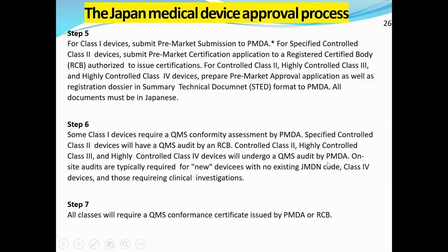So as you go higher and higher, more risk is involved. That is why an audit is required. So Japanese people will come and audit your facility, and on-site audits are typically required for new devices with no existing JMDN code, class 4 devices, and those requiring clinical investigation. So generally, you just have to remember class 3, 4 or class 2, 3, 4, where clinical evidence, clinical data is submitted for the new medical device. That facility has to undergo inspection by PMDA. So this is a common logic applied by each health authority for the critical devices that come under high risk.